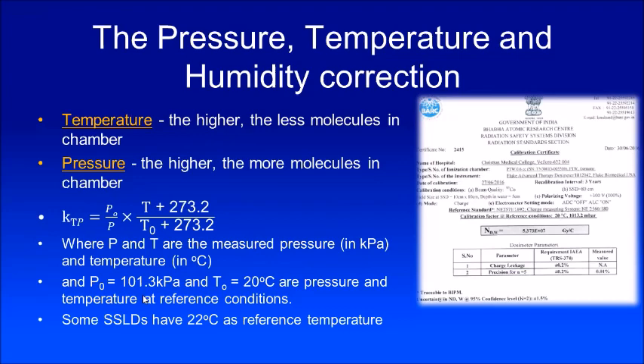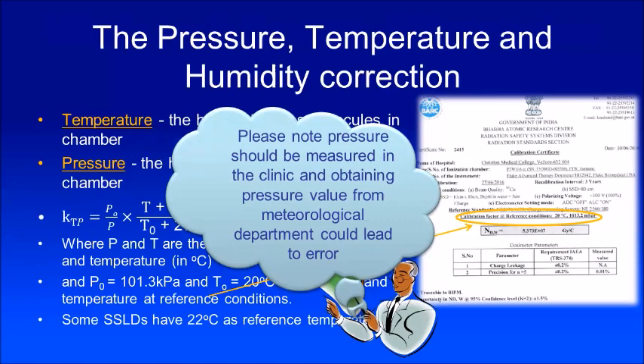Please note it is not always 20 degrees centigrade at which the SSDL calibrates — some SSDLs calibrate at 22 degrees centigrade, in which case T0 becomes 22. One has to be very careful about these values. Without looking at your calibration certificate, do not start your absorbed dose measurement.